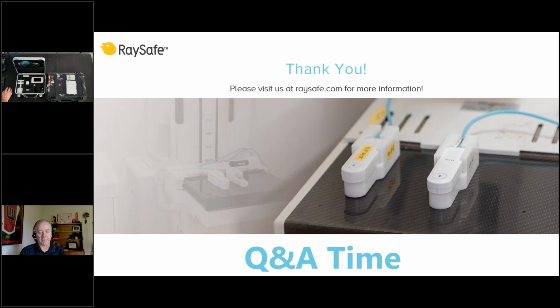And you want it to be transparent to X-rays if you're making measurements with AEC and ABC for fluoro, right? So you don't want to influence or drive up the kV and/or the mA on the ABC system. A battery would certainly do that. Or you don't want to affect the exposure time on an AEC rad system. It would certainly do that if the sensor was accidentally positioned over one of the ion chambers that control that. But with the RF sensor, it's basically transparent, so it won't affect any of that. Or if it does, very minimally.